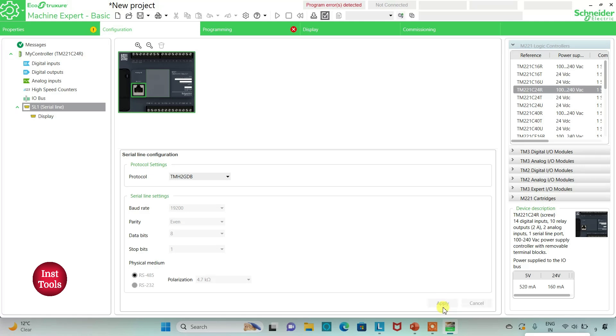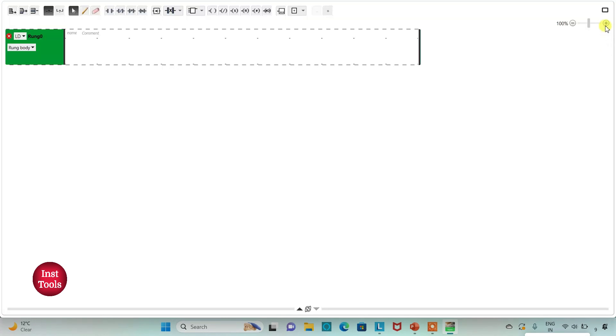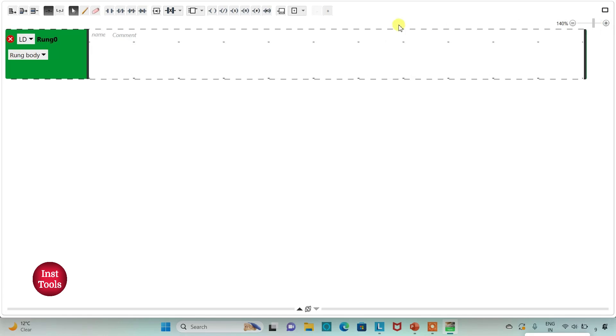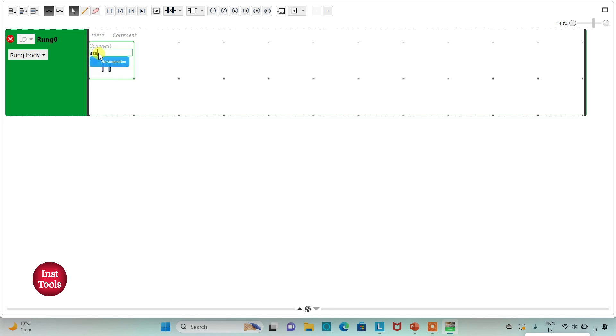After that I will go to Programming, where I will write the ladder diagram for this example. I will click on the full screen mode option and zoom in. Firstly, I will insert a normally open contact and assign the address I0.0 to it. I will also add the symbol 'Start Button' to it.